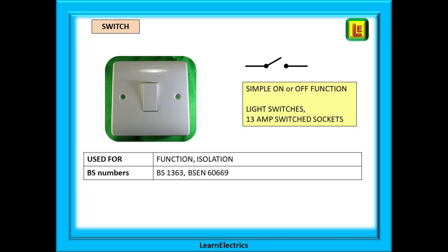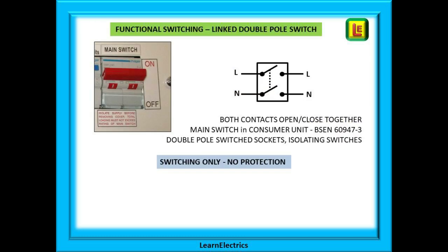The BS numbers for some typical switches that we often use are shown. Here we see a linked double pole switch such as those found in a typical consumer unit — the big red switch as many householders call it. It is used for functional switching: turning on or turning off the whole supply. The symbol is fairly straightforward. In reality the switch levers are physically joined together so that turning one off turns both off — two poles, one for phase and one for neutral. For a consumer unit this switch will be a BS EN 60947-3 and the meter tails will be connected into it. It is either on or off, with no protection from overload or short circuit currents, but it can be locked off for safe isolation.